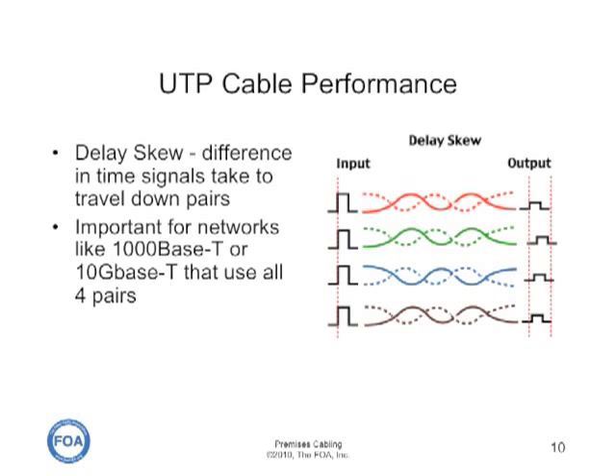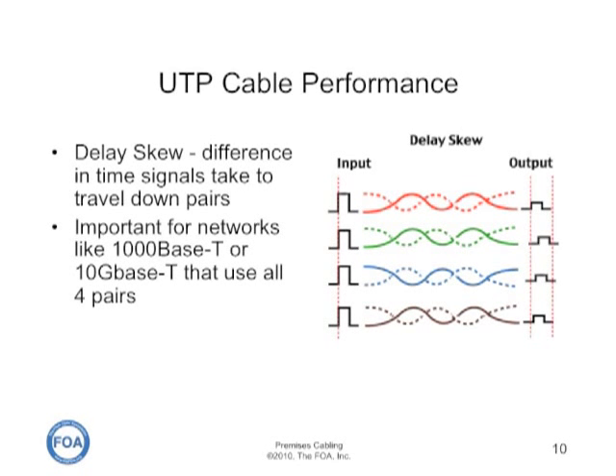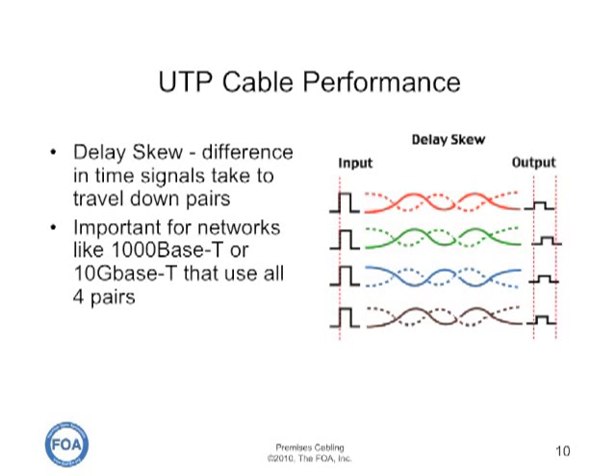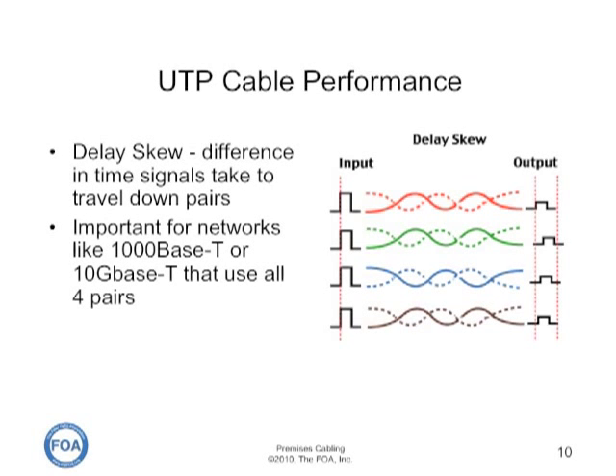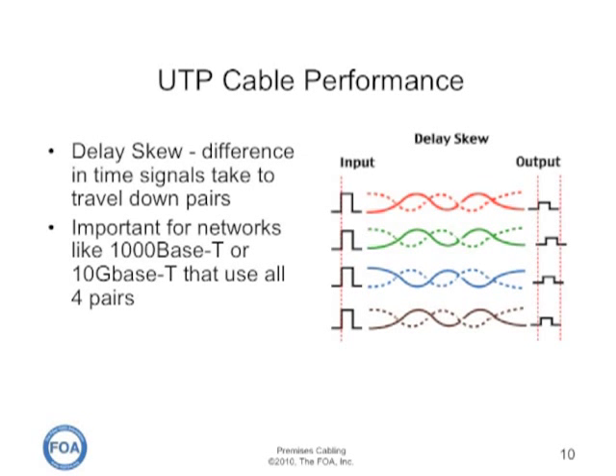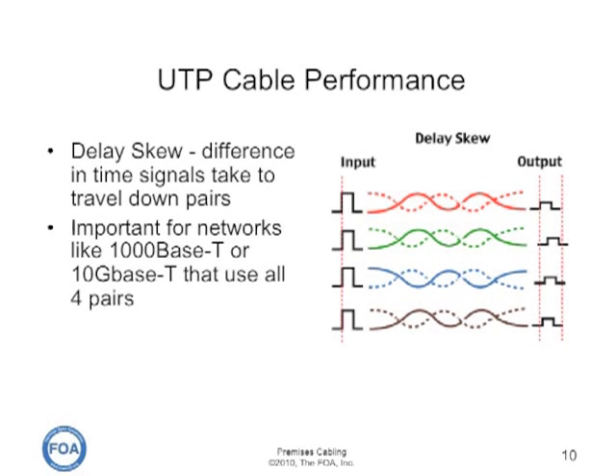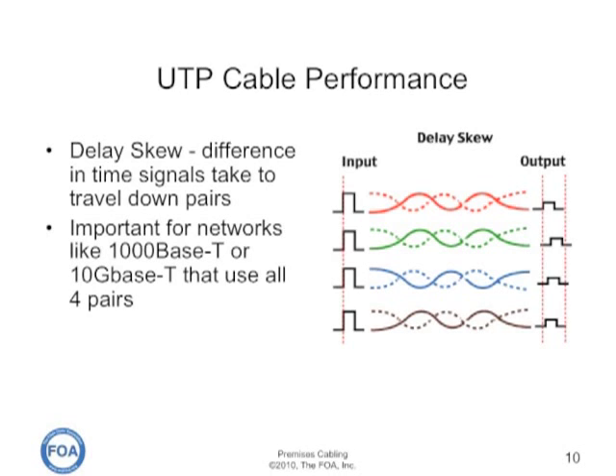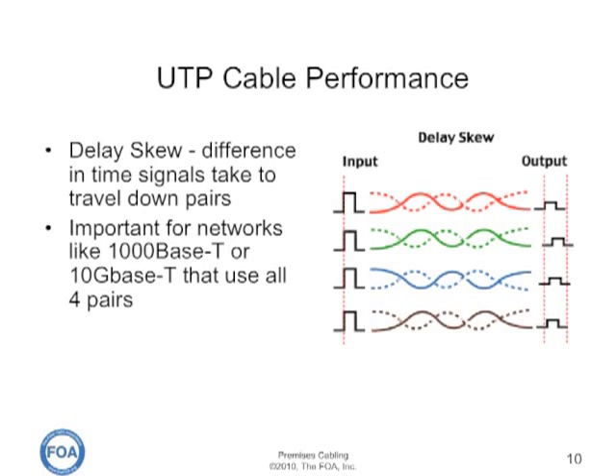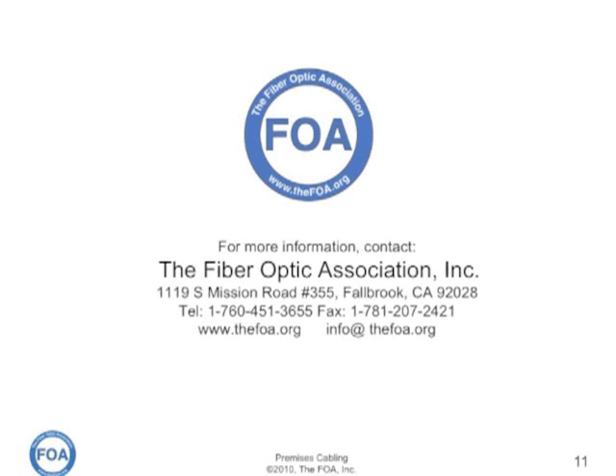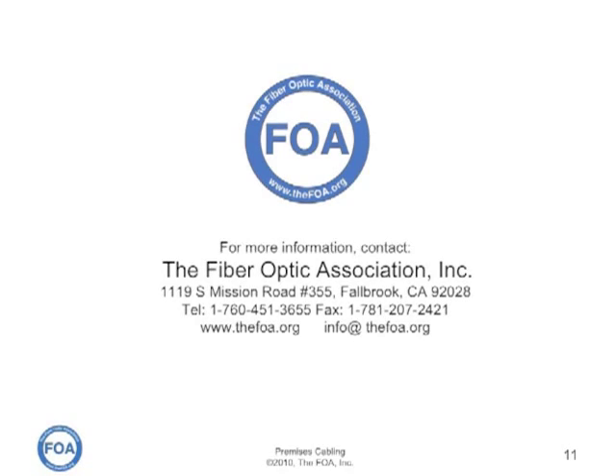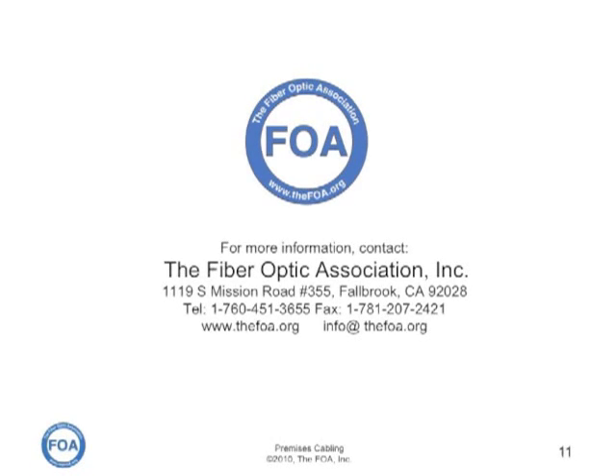Delay skew is an important test for cables used for transmitting gigabit Ethernet or faster. These systems use all four pairs, transmitting a fourth of the data on each pair, so it's important that they arrive within a specific time frame so they can be reassembled into one signal. The reason the time period may differ is that the different pairs have different twist rates, and a pair with more twist actually has more length of copper. This is another test that certifying testers always test for. More information on testing UTP cables can be found on the FOA website at www.thefoa.org.